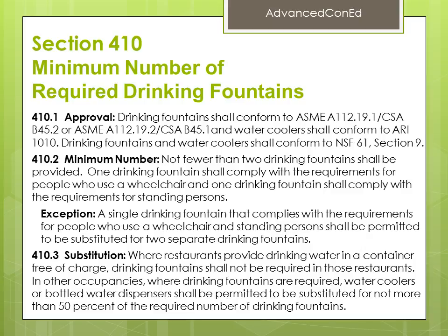Section 410 Minimum number of required drinking fountains. 410.1 Approval. Drinking fountains shall conform to ASME A112.19.1/CSA B45.2 or ASME A112.19.2/CSA B45.1, and water coolers shall conform to ARI 1010. Drinking fountains and water coolers shall conform to NSF 61, Section 9.